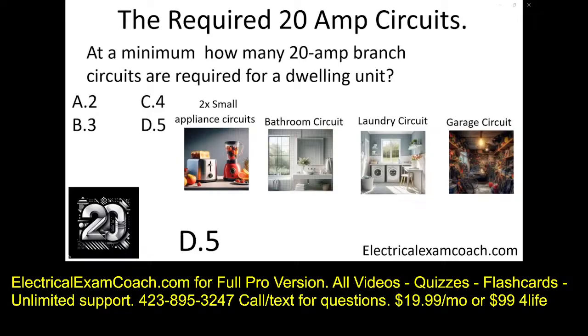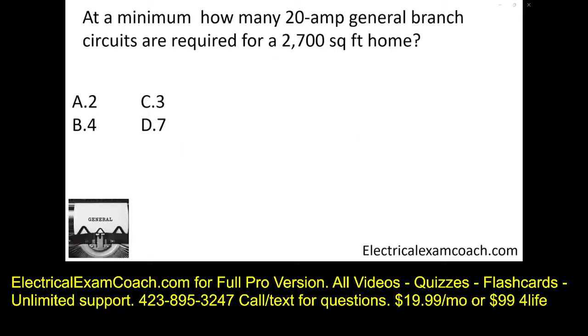At a minimum, how many 20 amp general branch circuits are required for a 2,700 square foot home? Now, your question may not say general. It may say for lighting and receptacles. You can keep an eye out for that. But usually if they give you the square feet, that's going to be the red flag for me that I'm calculating the general branch circuits. So how we're going to do this one, it's very simple. We're going to do it one step at a time.